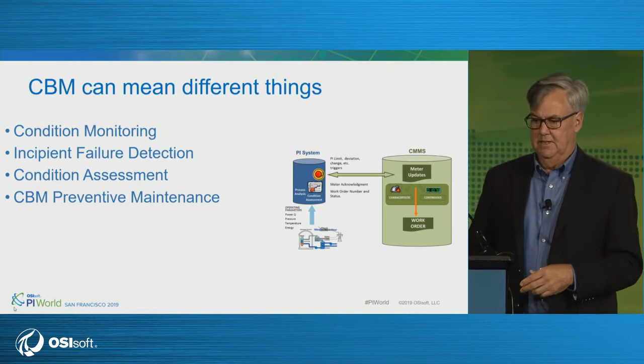Advanced Pattern Recognition actually came out of the aerospace and space industries. What it does is look at a group of signals related to an asset or system, based on how these variables have historically interrelated. It compares, in current time, how these variables are correlating today, and if they're out of spec by a certain amount, we can detect this difference and alarm on it. This is showing the darker black line as the actual value.